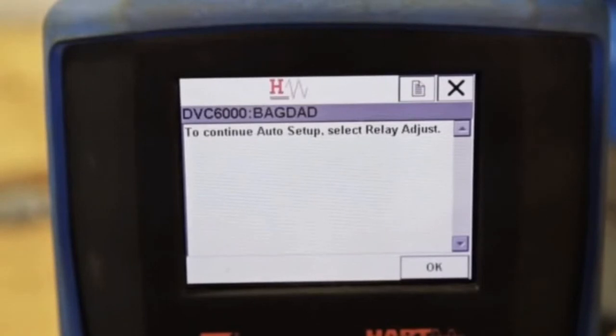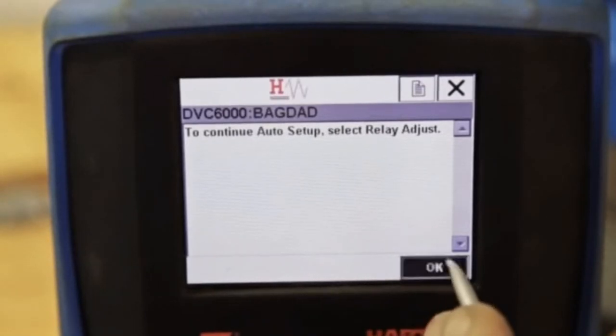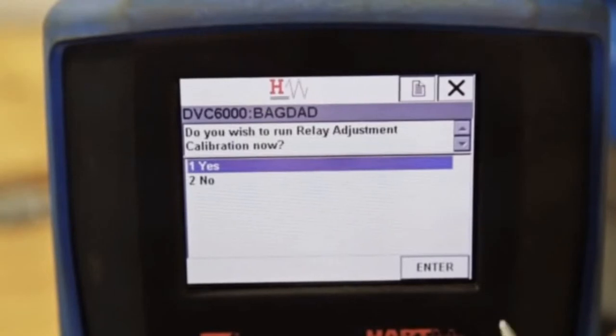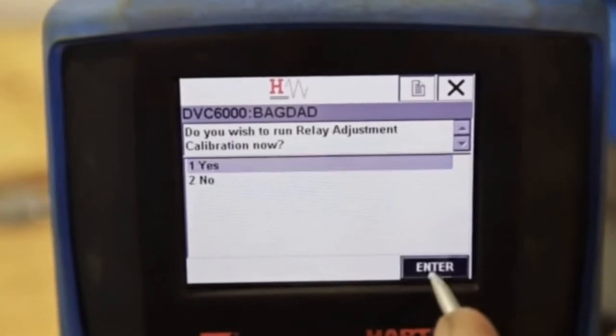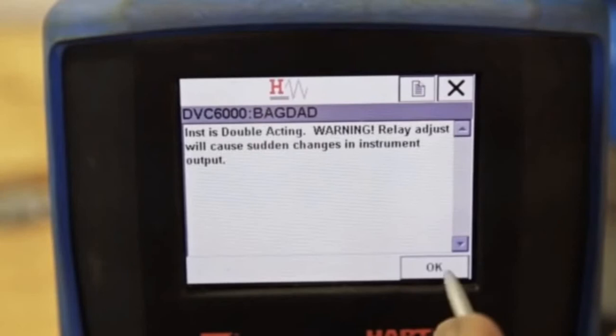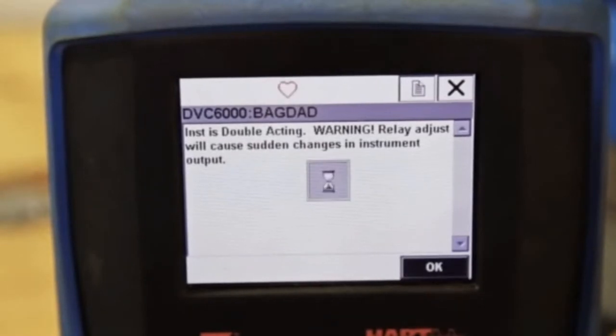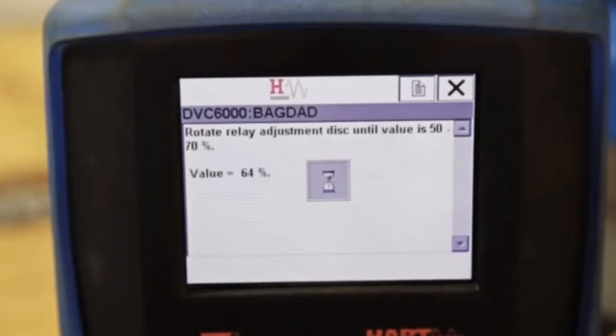Select OK to proceed with the relay adjust. Select Yes to run the relay adjustment calibration. Select OK and notice the warning. The relay adjust will cause sudden changes in valve position. This is the relay adjustment screen.